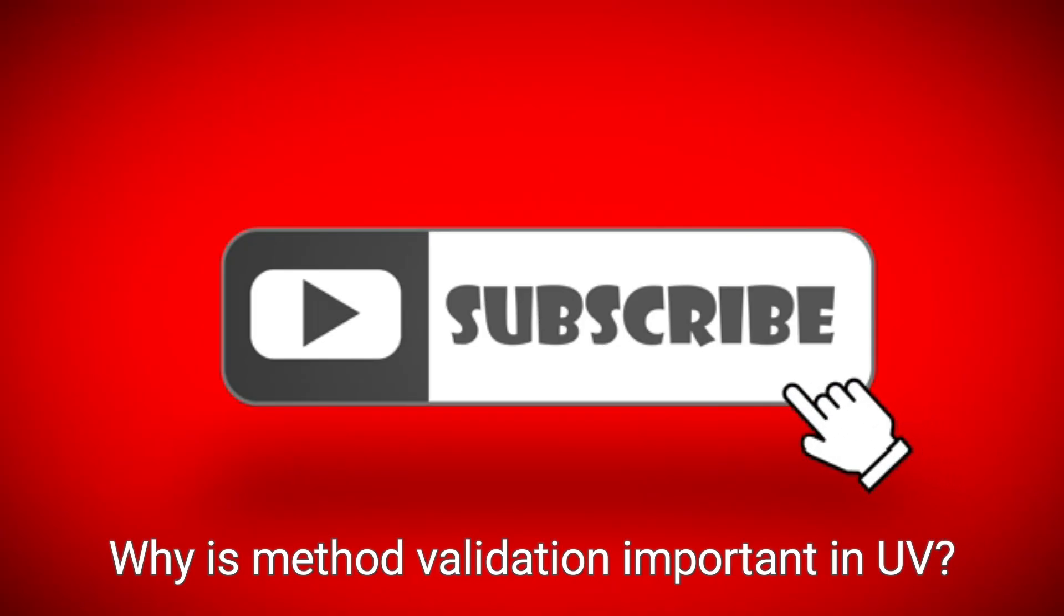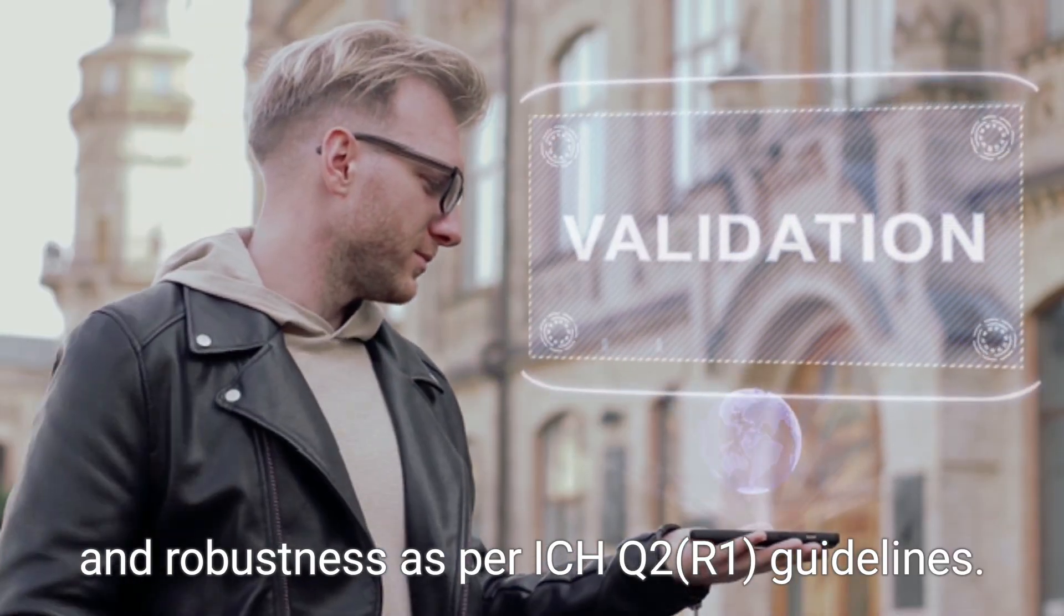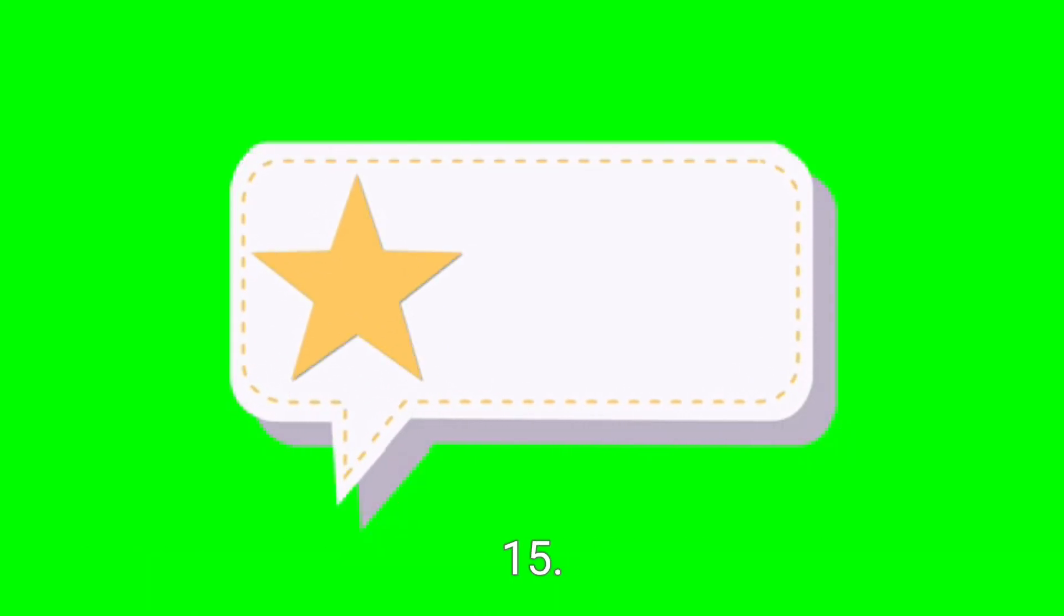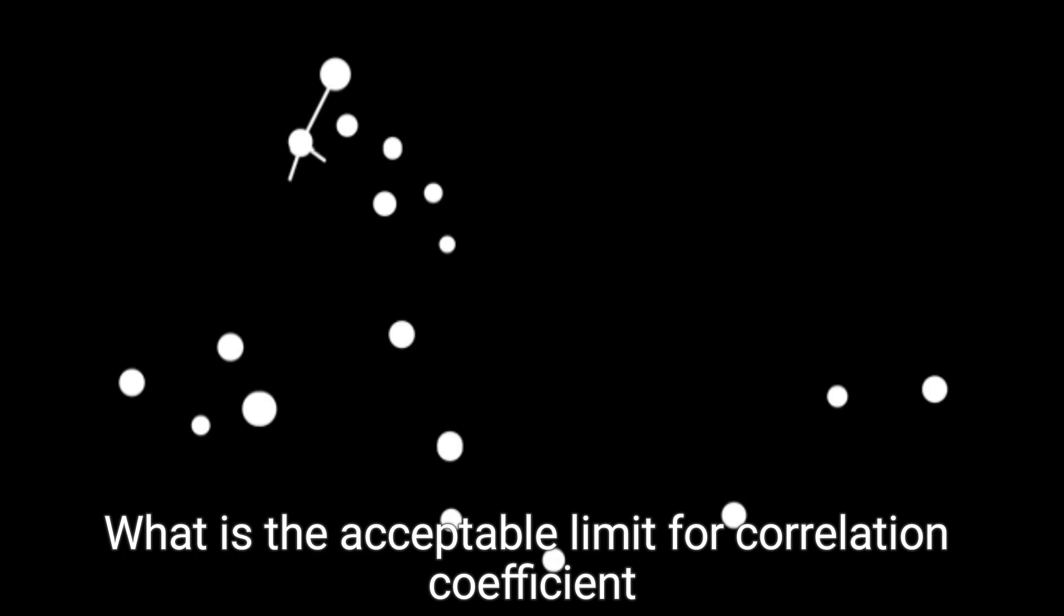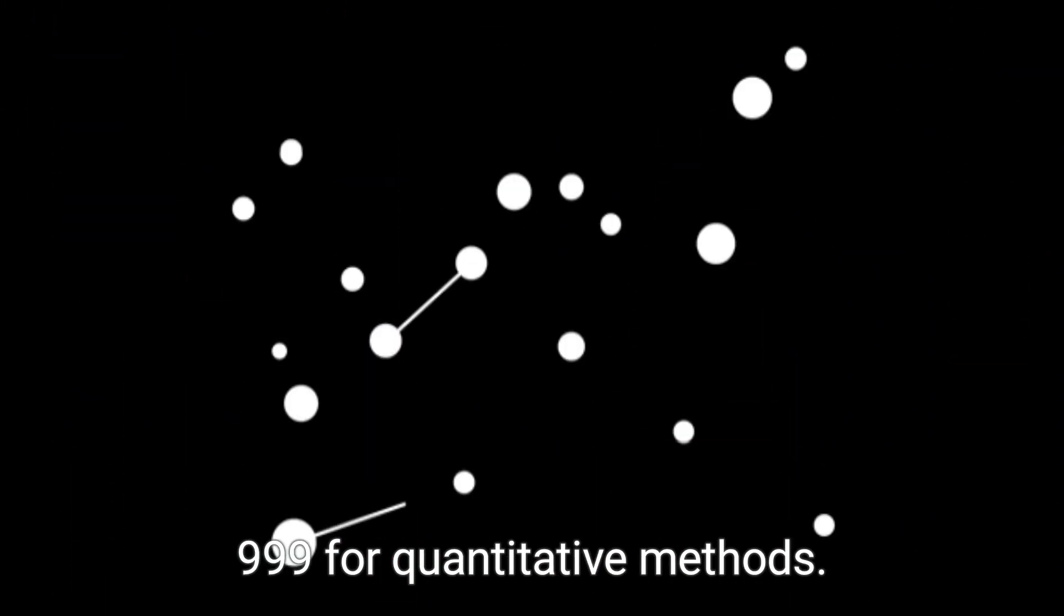Why is method validation important in UV? To ensure accuracy, precision, linearity, specificity, and robustness as per ICH Q2 R1 guidelines. What is the acceptable limit for correlation coefficient R squared in linearity? Not less than 0.999 for quantitative methods.